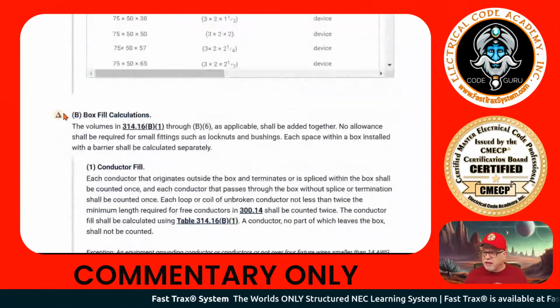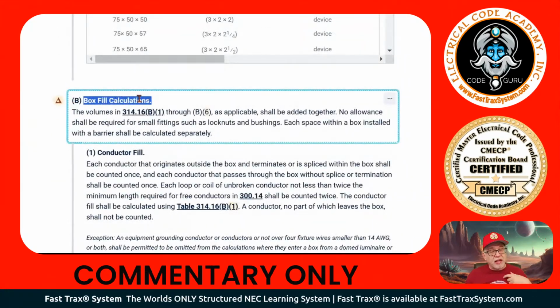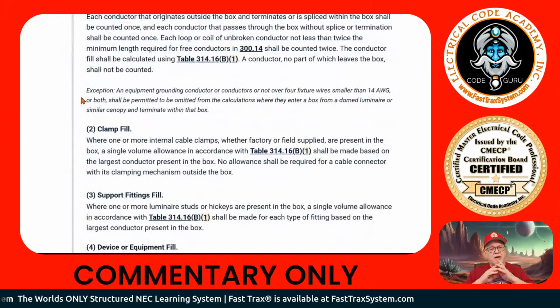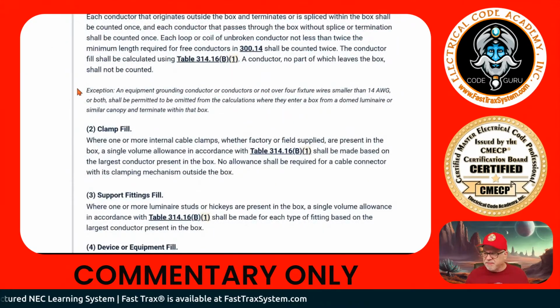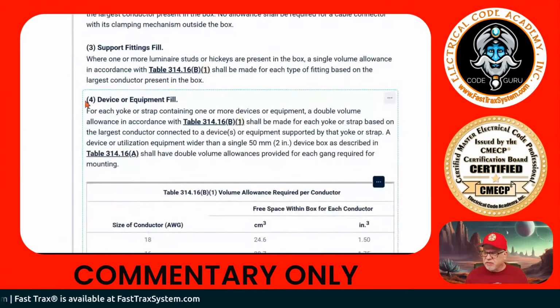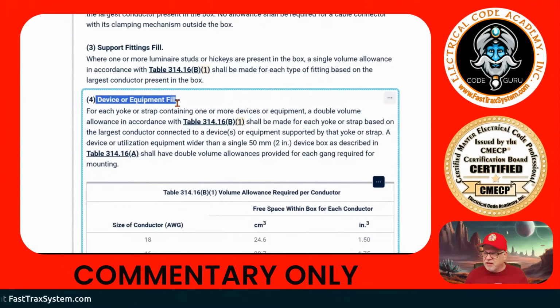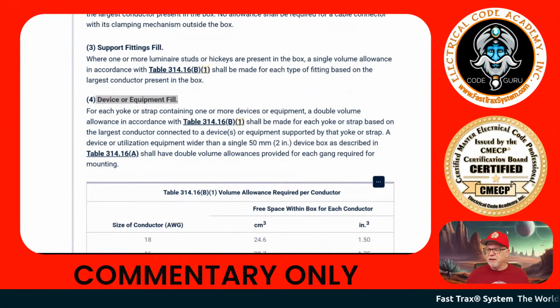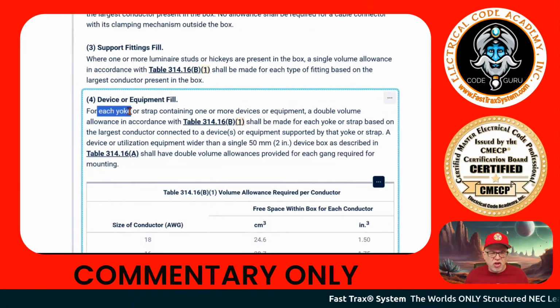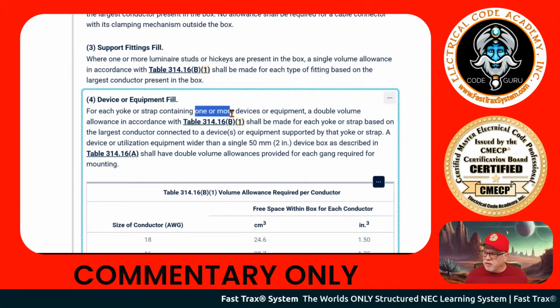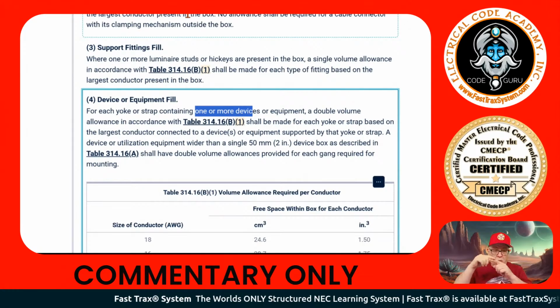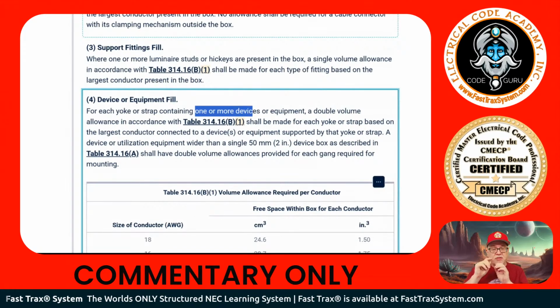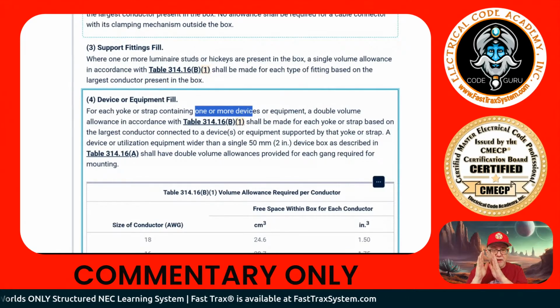All right, so what we want to go to is we're going to be scrolling down, and we got box fill calculations. That's what we're doing. And we're talking about a device, okay? And so we're going to scroll down and here, see what it says? Device or equipment. All right, so it says each yoke or strap containing one or more devices. So a simplex on a strap, that's fine. A duplex, it's still on a strap, it's fine. Triplex on one strap, it's fine. Switch, one strap, it's fine.